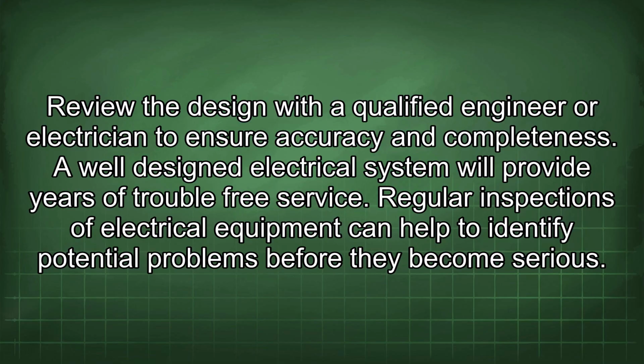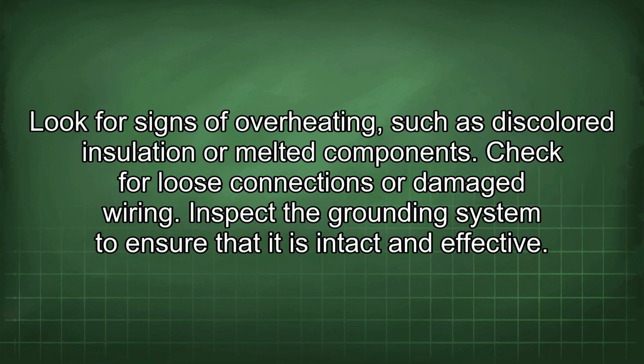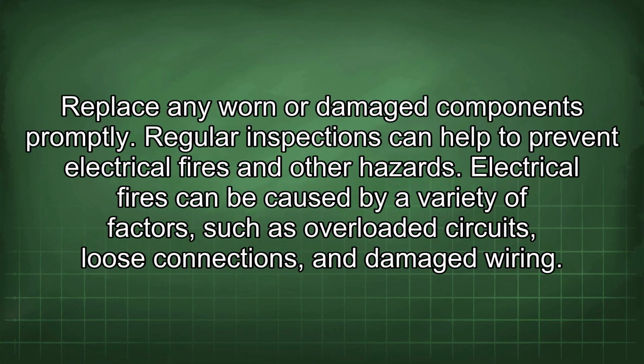Regular inspections of electrical equipment can help to identify potential problems before they become serious. Look for signs of overheating, such as discolored insulation or melted components. Check for loose connections or damaged wiring. Inspect the grounding system to ensure that it is intact and effective. Replace any worn or damaged components promptly. Regular inspections can help to prevent electrical fires and other hazards.